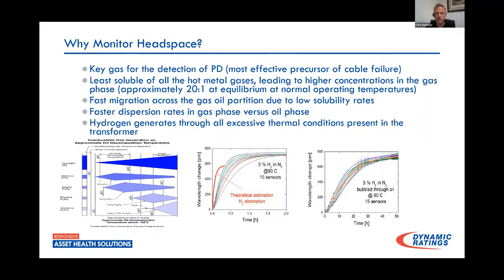Also, there's the sensors themselves. So it takes the sensors in oil, and this was actually some that were placed in oil, and you can see there were 15 sensors placed. 5% hydrogen mixed in a nitrogen base was sparged through these sample cells, and you can see that for measuring in gas, where we're taking our gas measurements, we're about 1 hour till we reach that full saturation point at the sensor. So 1 hour's worth of time. Whereas if we go to 15 sensors that are installed in oil in the transformer, we can see that that's up to about 50 hours before we reach that full saturation. Now, this is also being done in a very predictable lab setting where we're not dealing with leaks or that type of thing. So again, if you get out in the real world, almost everything leaks at some point. That's going to cause this to be even slower, as we're not going to get that equilibrium.